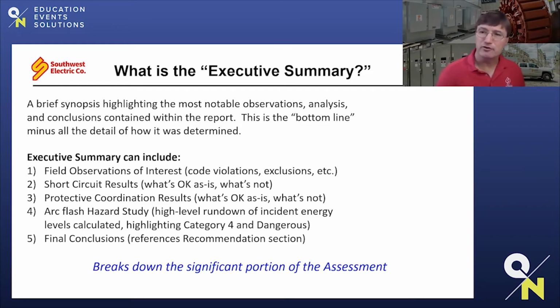Most of the time, the majority of the analysis is going to reveal values that are considered fairly normal, fairly manageable, fairly easy to deal with. The executive summary is intended to highlight the items of interest, usually energy levels of a high nature, any findings of damaged equipment that they might have uncovered, issues where protection may not be sufficient or maybe miscalibrated.